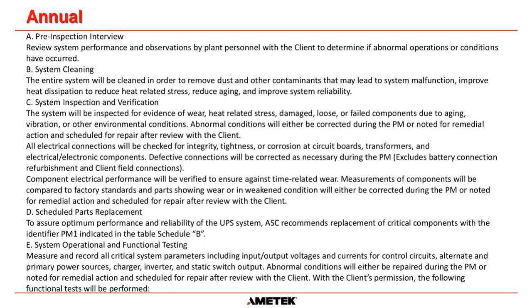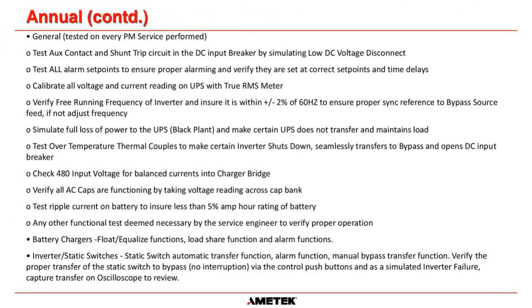So we check all the inputs and outputs, the control circuits, the primary supply, the alternate supply, the charger, the inverter, the static switch outputs, and we make sure that they are all working correctly. We also test all the auxiliary contacts and the shunt trip circuit in the DC breaker by simulating a low DC voltage. And then we check as many of the alarm set points as we can to make sure if you do have a live alarm on your system that it reports to your DCS. We also calibrate all the voltages and current readings. We verify the free running frequency of the inverter. To do that, we switch off the bypass supply and we make sure the inverter runs at 60 Hertz plus or minus 2%.